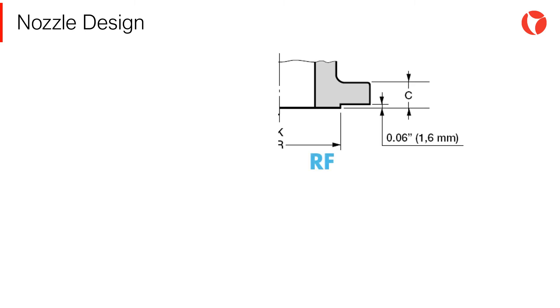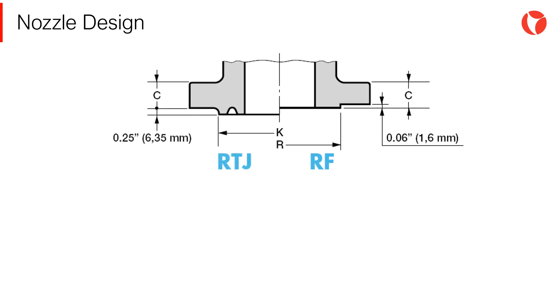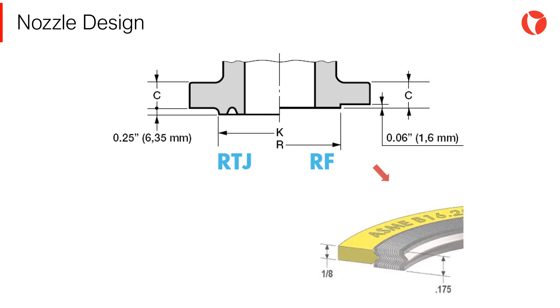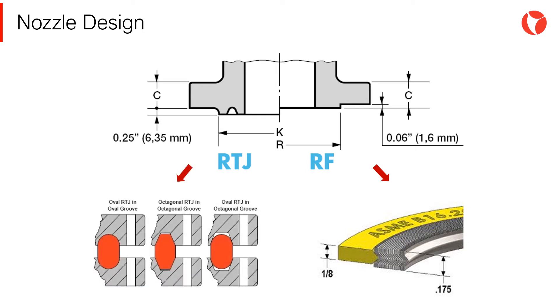There are several types of flange facings, selected upon the seal tightness requirement. The most used flange facings in pressure vessels are raised-face flanges — the most common type used in process plant applications, where the gasket surfaces are raised above the bolting circle face. Ring joint flanges are typically used in high-pressure services, class 600 and higher, and/or high-temperature surfaces above 427°C; they have grooves cut into their faces for steel ring gaskets. For RF flanges, steel spiral-wound gaskets are normally used, and for RTJ flanges, gaskets can be octagonal or oval. Gasket materials depend on operating fluids, being typically stainless steel SS304.